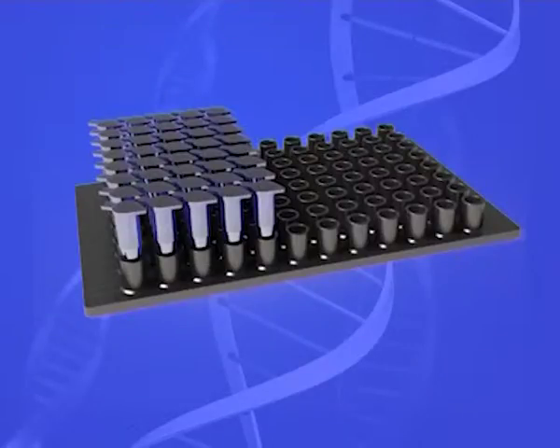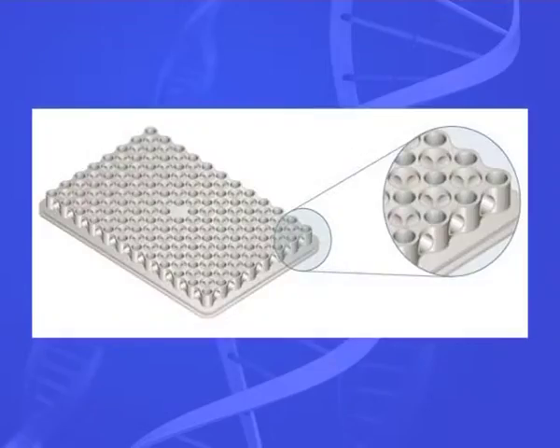The thermal cycler heats and cools the reaction tubes to achieve the temperature required at each step of the reaction. Many modern thermal cyclers make use of the Peltier effect, which permits both heating and cooling of the block holding the PCR tubes simply by reversing the electric current. Thin-walled reaction tubes permit favorable thermal conductivity to allow for rapid thermal equilibration. Most thermal cyclers have heated lids to prevent condensation at the top of the reaction tube.